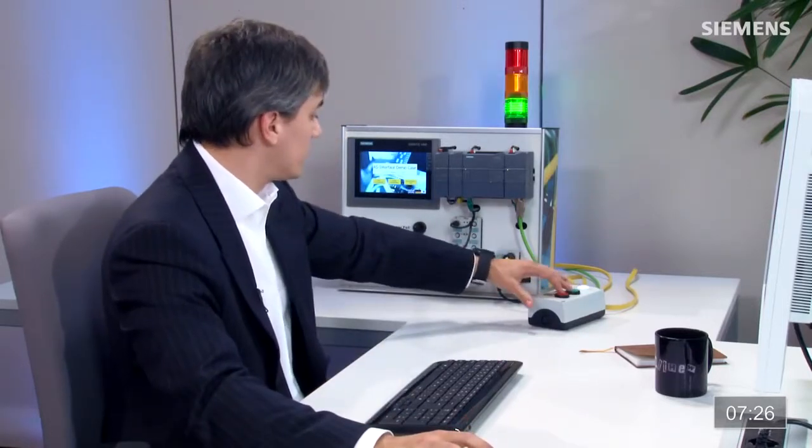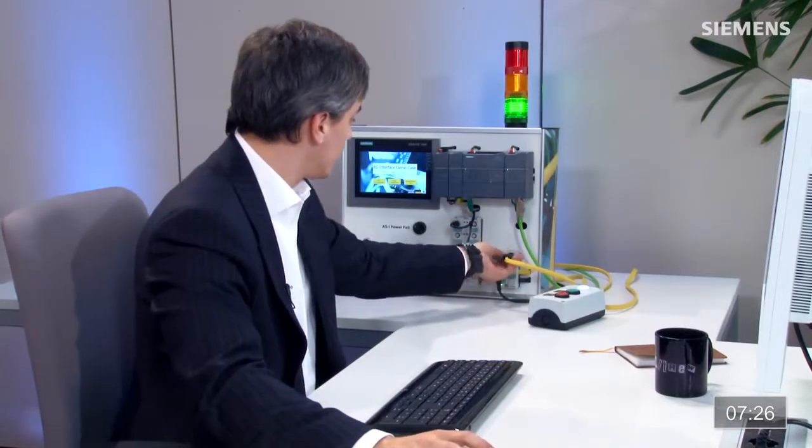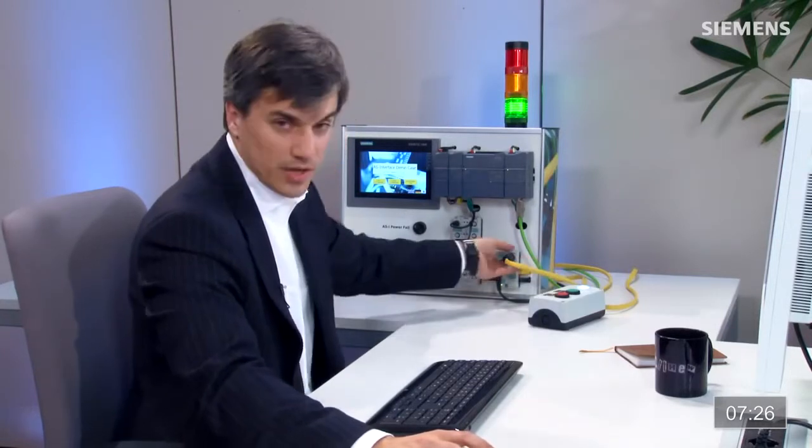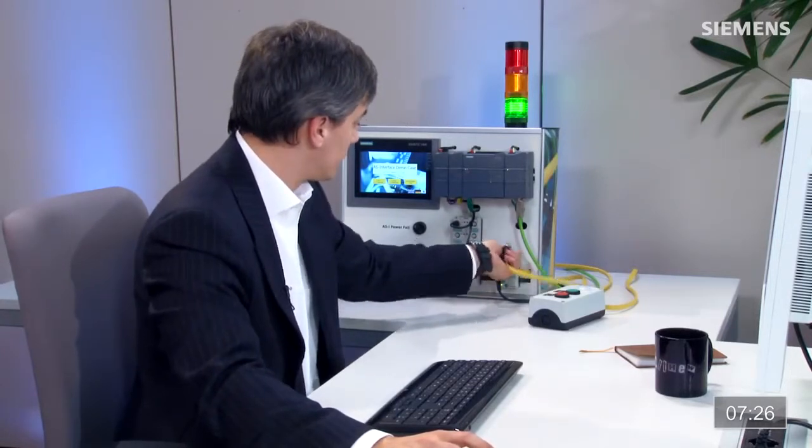All I got to do now is go here and see I can hit the Start-Stop station. Everything runs the way it's supposed to. And in fact, I can go here and fault out the AS-i network. And this is the actual input for our Start-Stop station. It should fault. So the fault logic is working the way it should be.